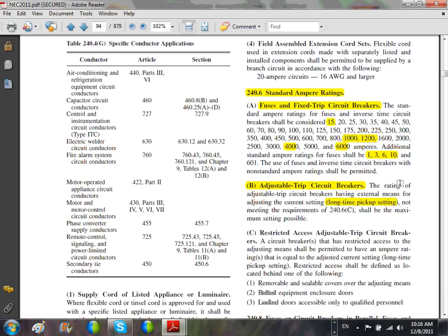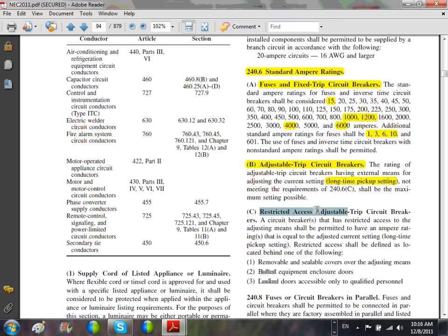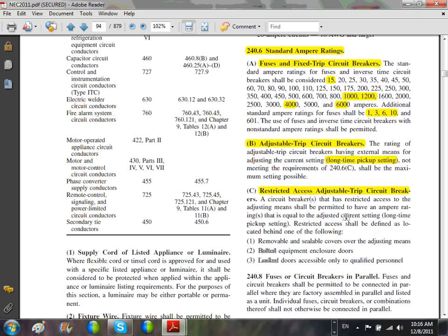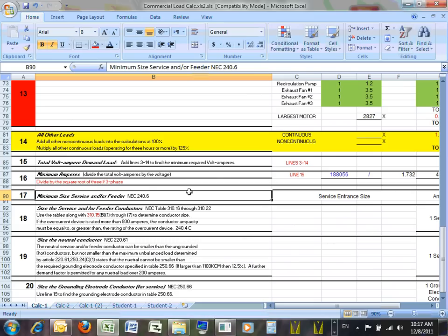Yes. It becomes a big deal, guys, when we go for systems higher than 600 amp. You start using adjustable circuit breakers and you size based on long time pickup. Anyway, highlight this one for me, please. It will tell you that you have to put them under restricted access adjustable trip.